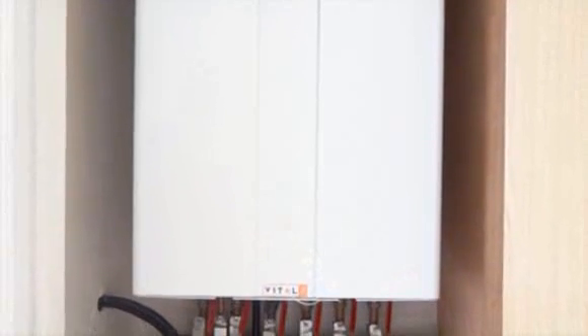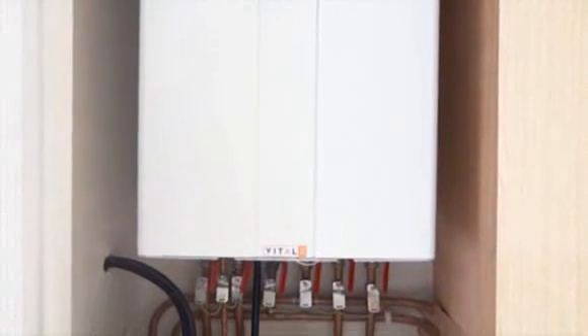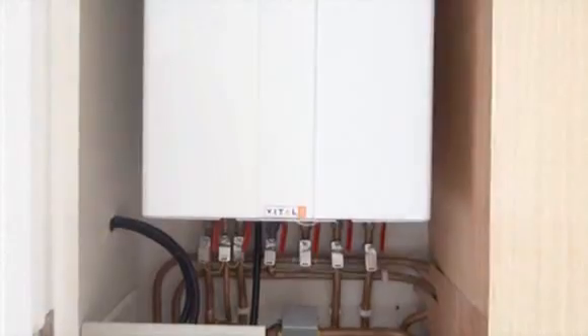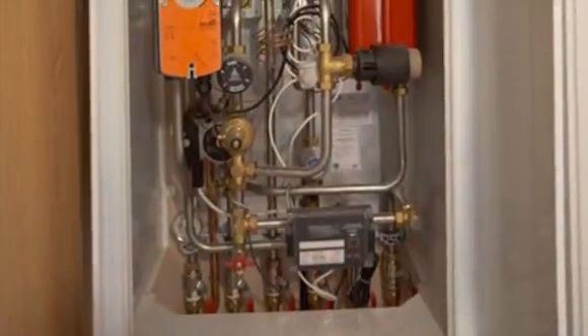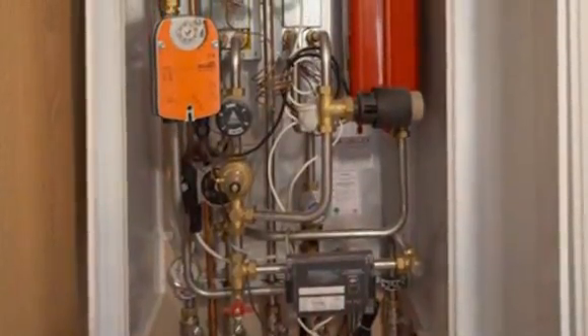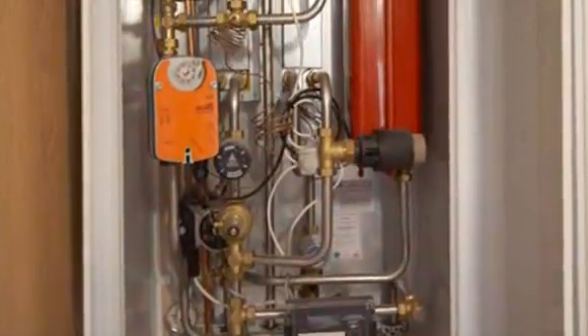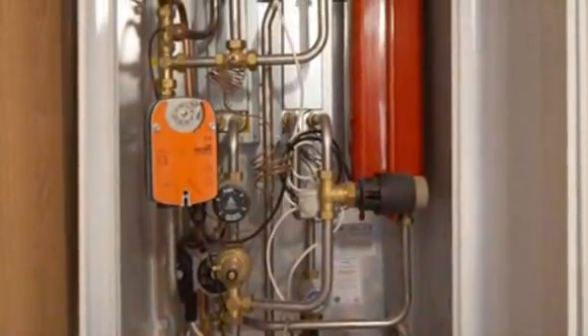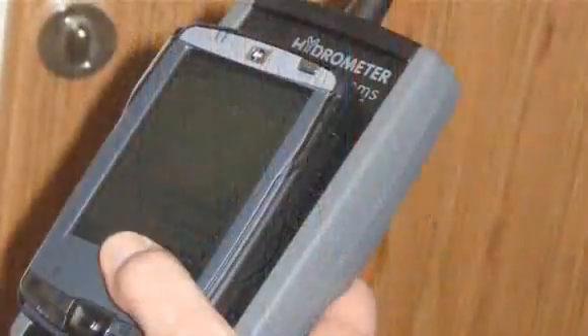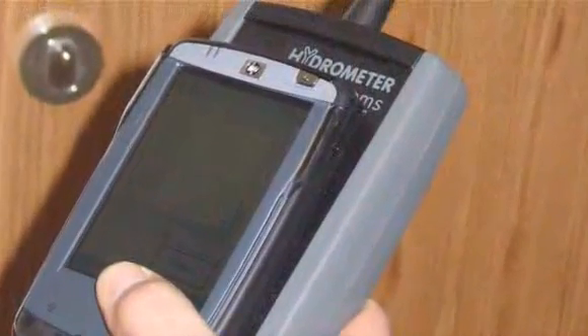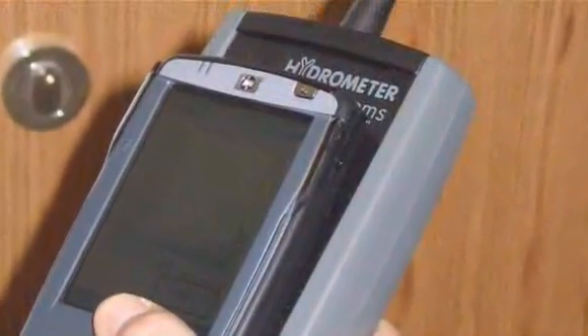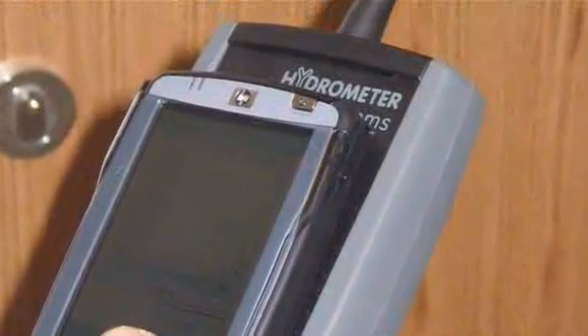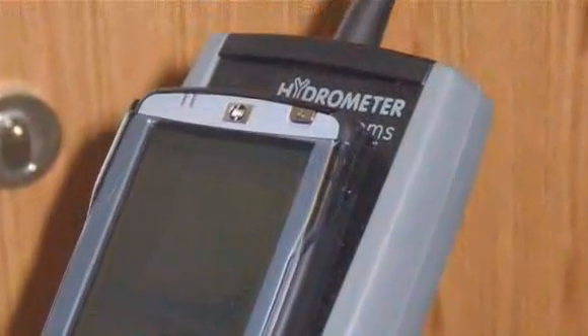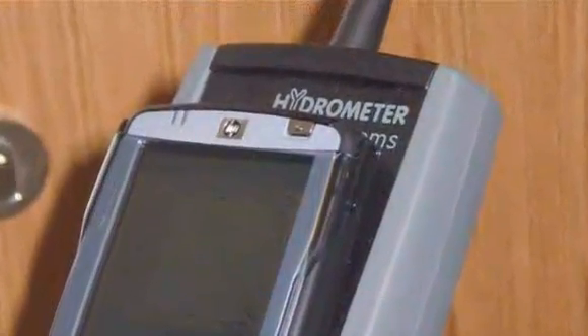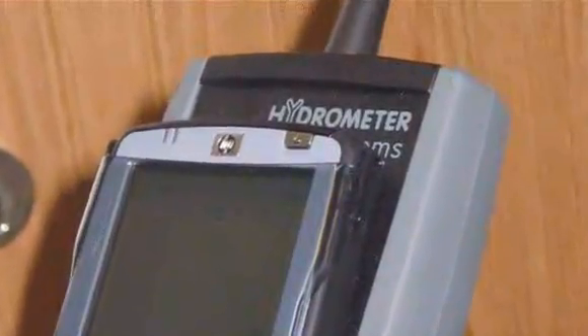In each dwelling, a hydraulic interface unit, or HIU, is installed. The HIU has a plate heat exchanger installed that separates the dwelling's internal space heating system from the primary heating distribution system. An ultrasonic heat meter measures the amount of heat taken from the common heating distribution system by each individual dwelling, which is also incorporated into the HIU.